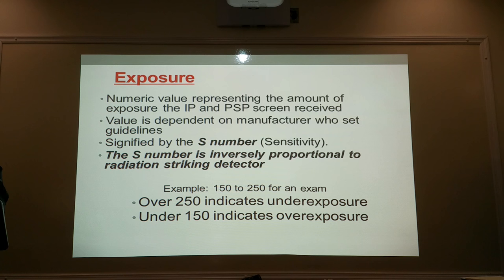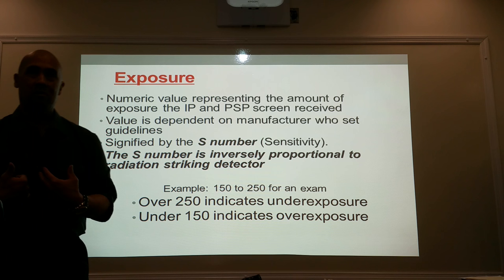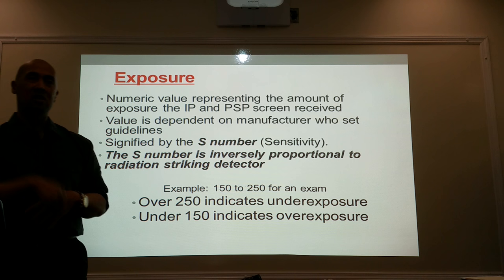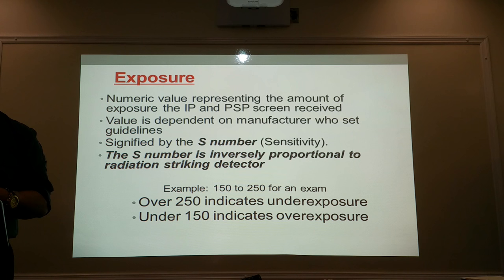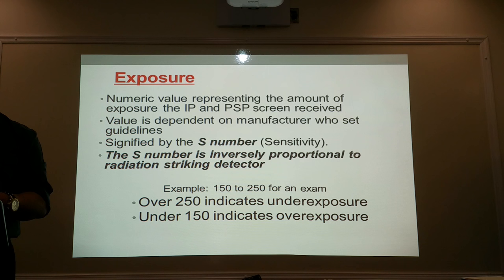As a quality assurance manager, not only am I going to look at the images coming up as my technologists perform their studies, I'm also going to be looking at that S number to make sure my technologists are operating within safe limits. No longer can I depend on the quality of my image because the quality is always going to be good. Before, if it was too dark or too light, I knew whether or not my technologists were doing badly.